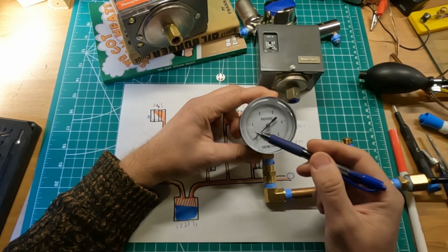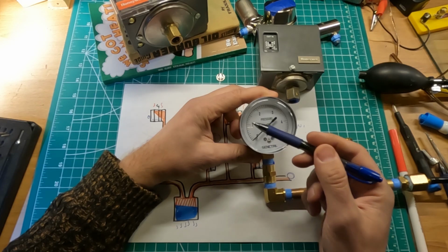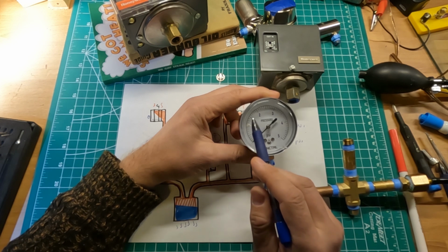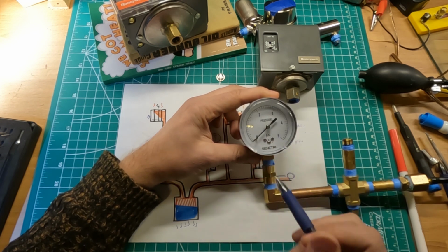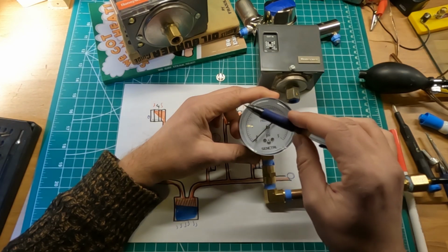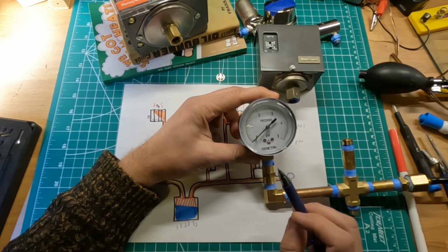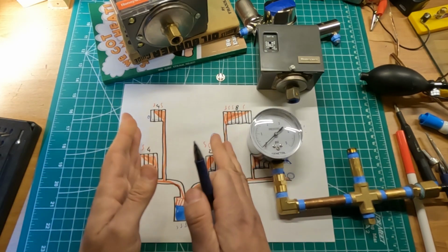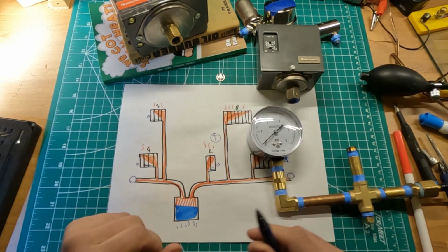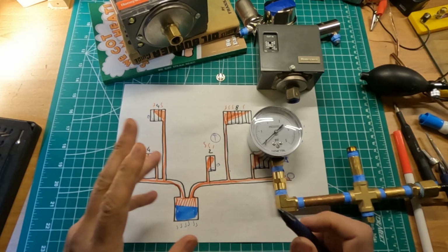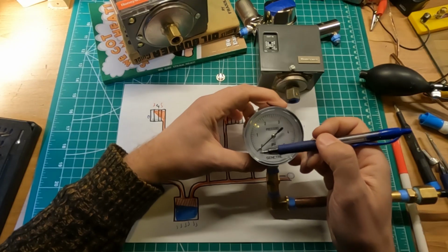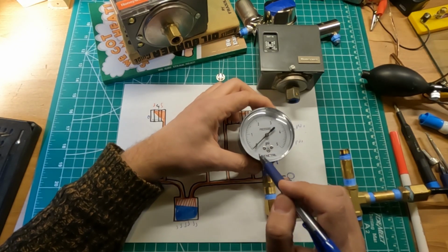On my system, which I have set right now to shut down at 1.5 psi, it goes from 1.5 to 0 in around 45 seconds. So it takes around 4.5 minutes to build up to 1.5 psi from the moment all those vents closed, and then 45 seconds to go to 0. So yeah, that will be a good working system. That said, my next step is going to be to get a Vaporstat, so that the system can shut down before it reaches even 1 psi.